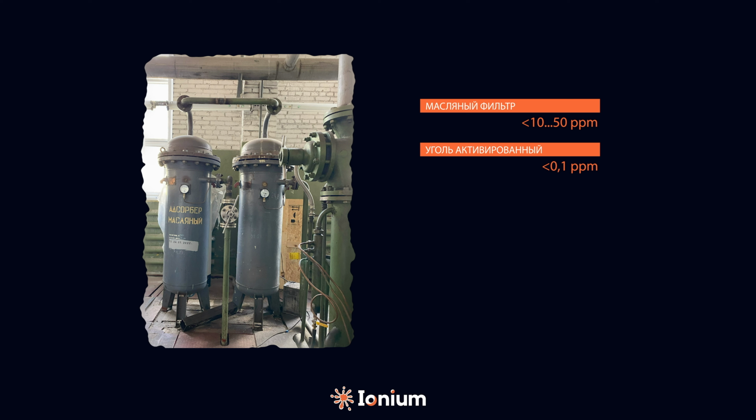Deep oil removal effectiveness relies on the helium's inlet temperature at the adsorber. Therefore, additional cooling using the chiller's intermediary water circuit is a technically sound solution. When the helium temperature at the inlet increases, compared with entering the adsorber at 16 degrees Celsius, the sorbent capacity, over a range from 0 to 20 degrees Celsius, will decrease by an average of 5 to 10 percent in oil sorbent capacity. Oil concentration will rise to 0.5 ppm, maintaining a constant sorbent layer thickness, due to warm adsorbers using activated carbon.